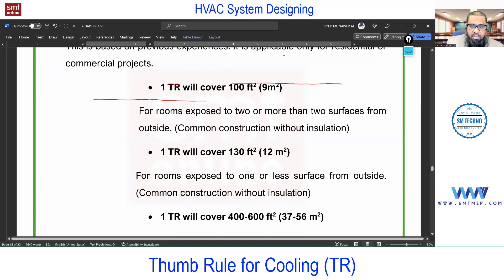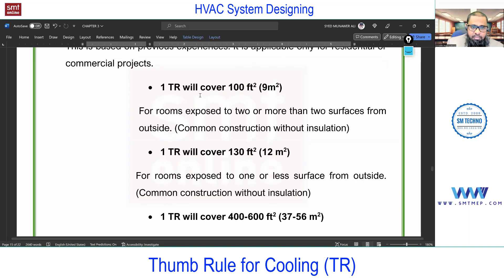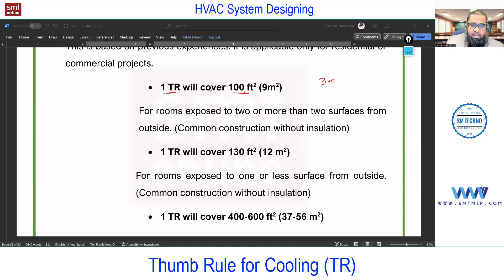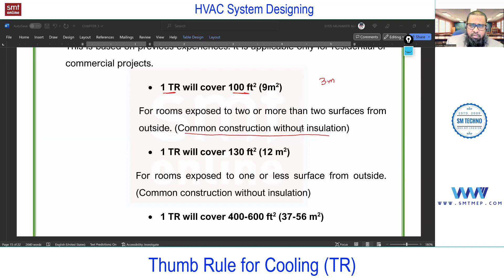You need to memorize these values — they can be asked in interviews. One ton of refrigeration (TR) will cover 100 square feet of area, considering a standard height of 10 feet (3 meters). So one ton covers 100 square feet. Note that this is outdated — it's based on old-school practice and assumes common construction without insulation.